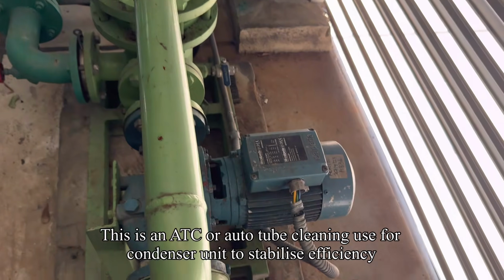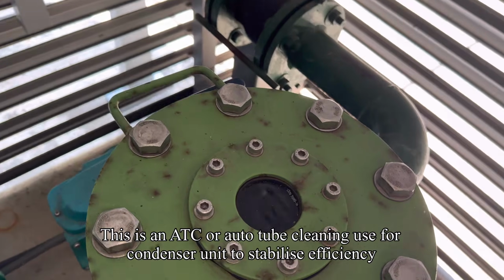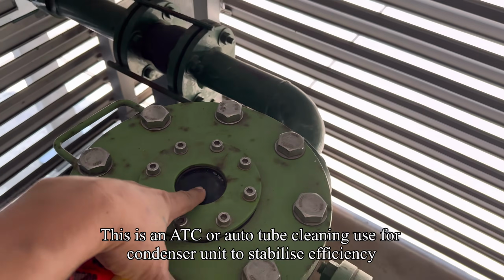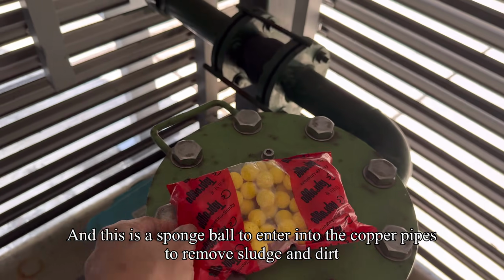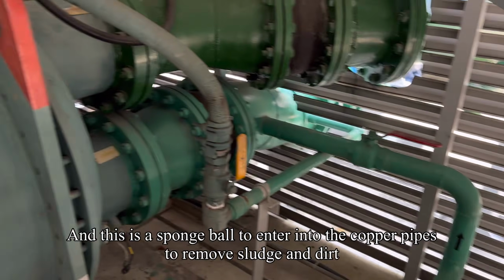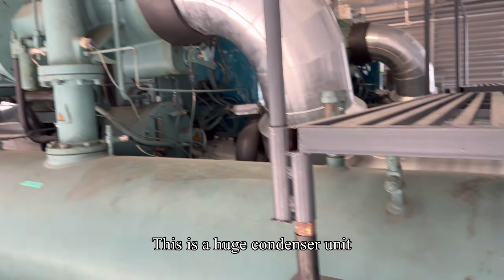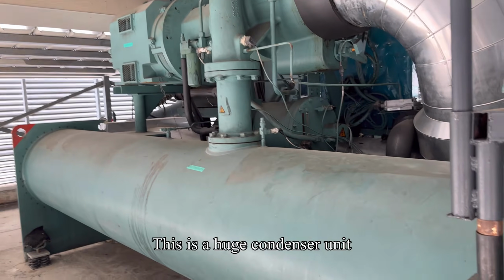This is an ATC, or auto-tube cleaning unit, used for a condenser unit to stabilize efficiency. And this is a sponge ball to enter into the copper pipes to remove sludge and dirt. This is a huge condenser unit.